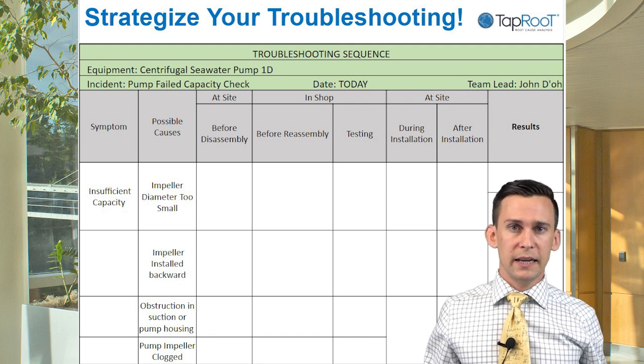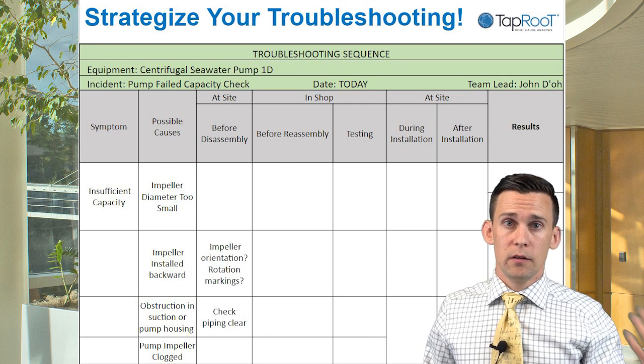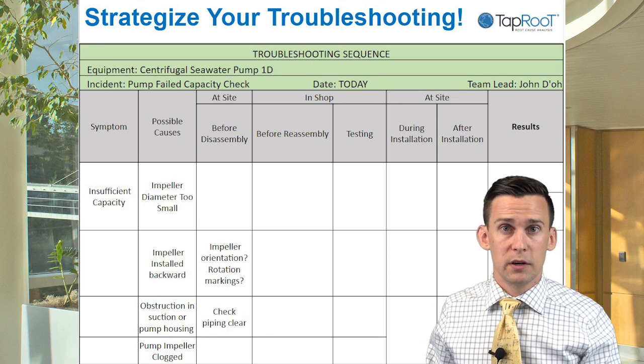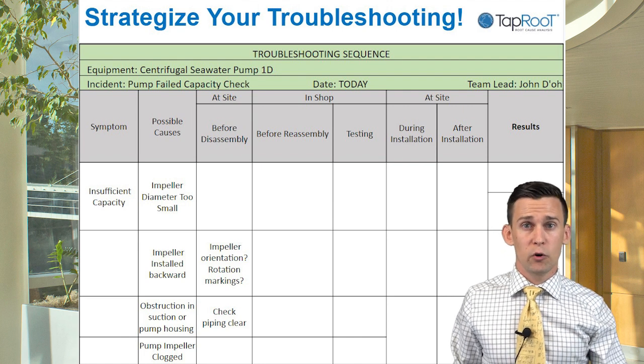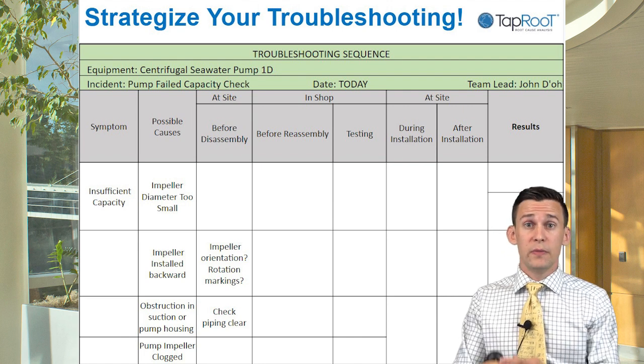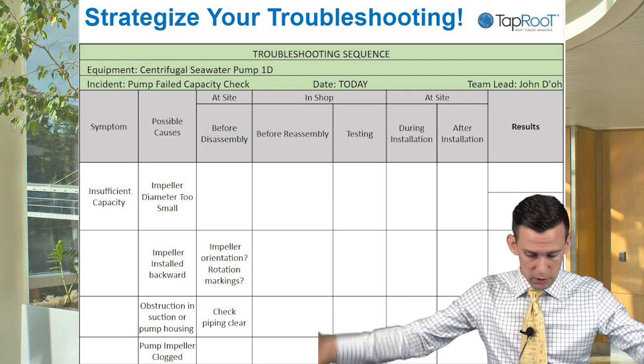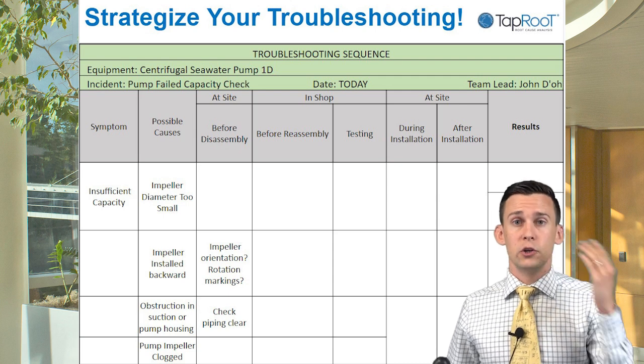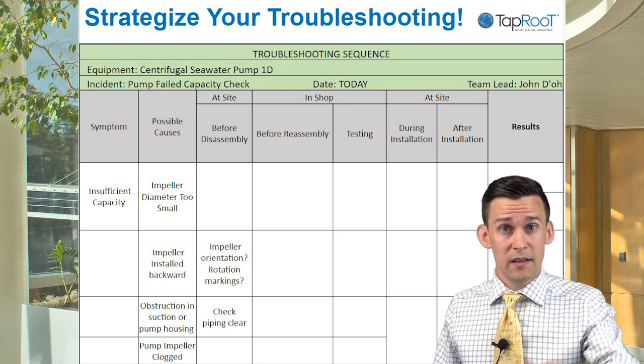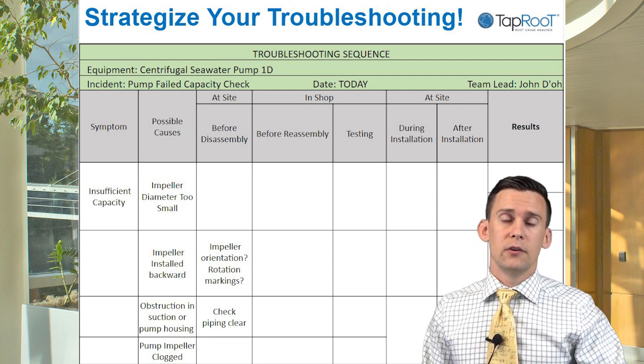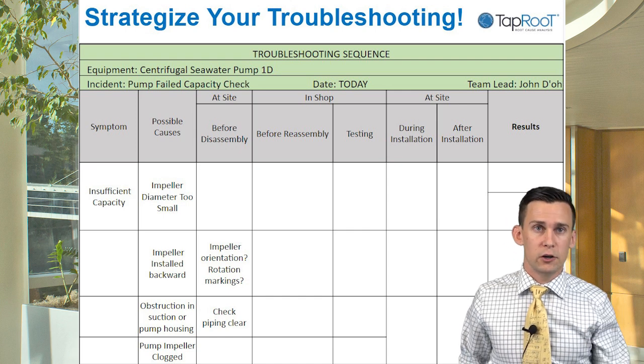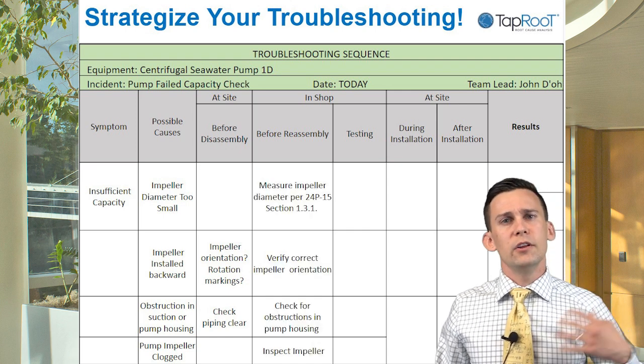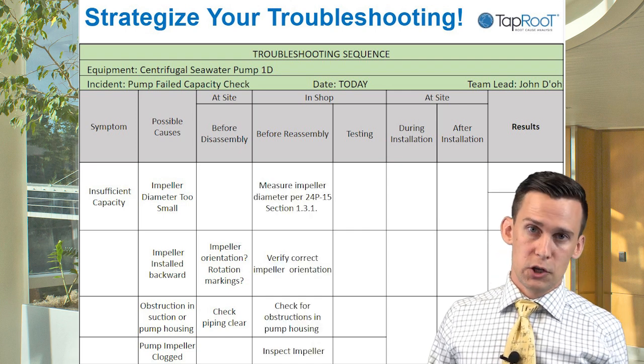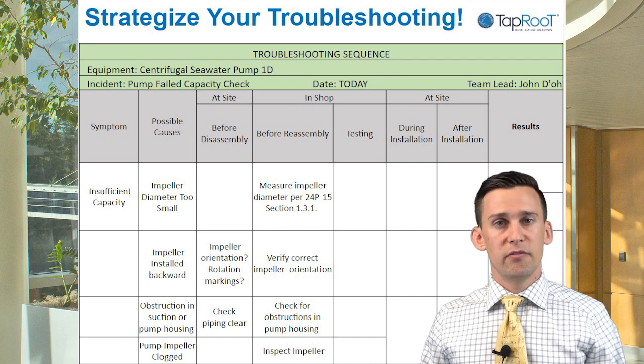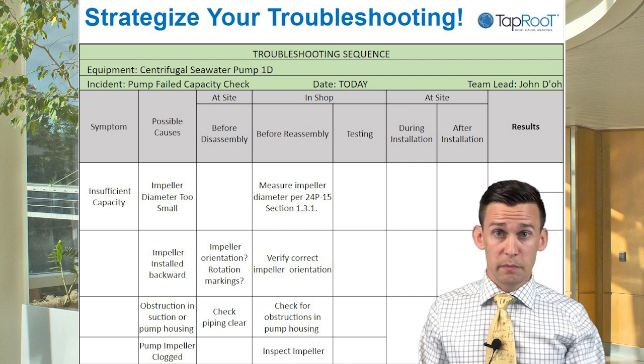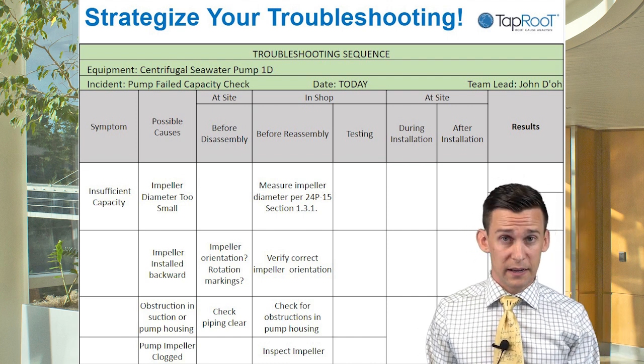So building our plan to troubleshoot, there are things we want to do before disassembly. Can we check the impeller orientation? If you tear the pump apart and have all your pieces laying there in front of you, you're going to lose the data on which way the impeller was installed. Also, when you pull the pump out, make sure you check your piping. Then you want to go back and measure your impeller diameter and verify, as you're putting it back together, that you're putting it in the right spot.